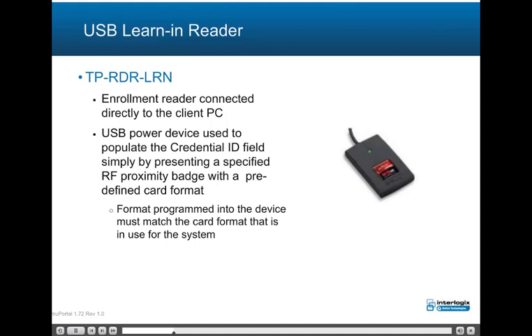The TP-RDR-LRN USB Learn and Reader is an enrollment reader connected directly to the TruePortal client PC. It is a USB-powered device used to populate the credential ID field simply by presenting a specified RF proximity badge with a predefined card format. The format programmed into the device must match the card format that is in use for the system.